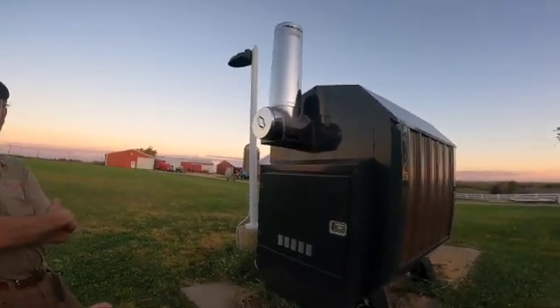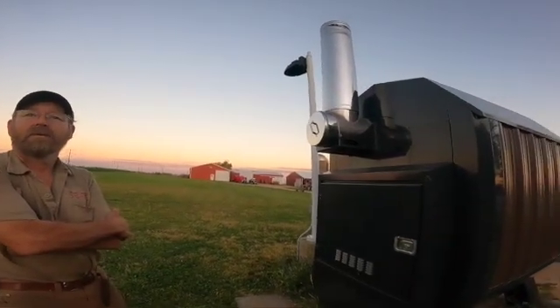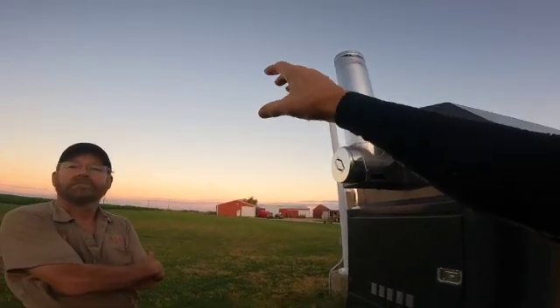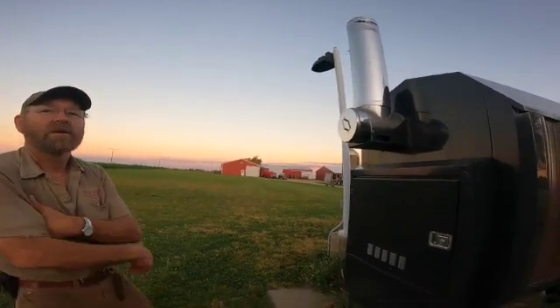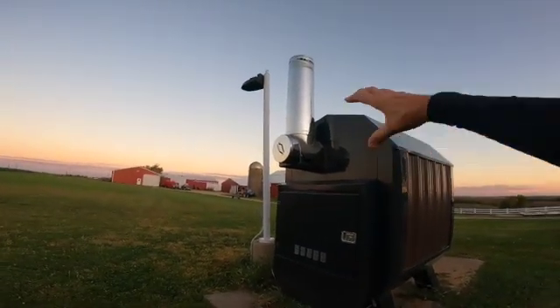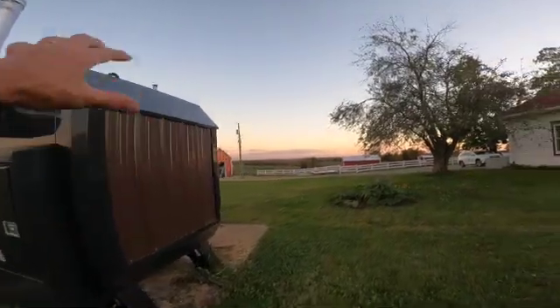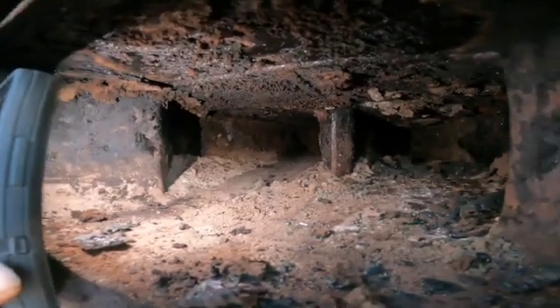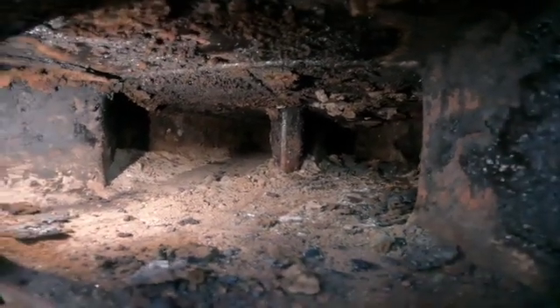You get some steam. I'm getting into biochar and we're designing a kiln — I was thinking about my central boiler where I get a fair amount of smoke, and having the draft into a hot kiln would double-burn any residual smoke. Brian was saying on this furnace you're not going to have a lot of extra smoke to double-burn, because they've got refractory cement in here that helps it get a double burn and burn hotter. So there's secondary combustion happening — that's why there's not a lot of smoke exiting. There's a secondary combustion chamber.